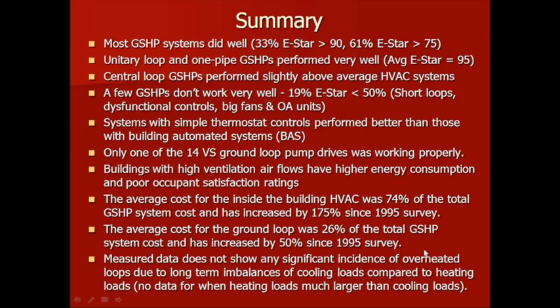Only one of the 14 variable speed ground pumps was working properly. As I mentioned, we had some complaints when the ventilation air equipment size was large. We had a lot of comfort complaints. And as I mentioned before, the inside the building cost was 74% of the total cost of a ground source heat pump system, the HVAC system, and it's gone up 175% since 1995.